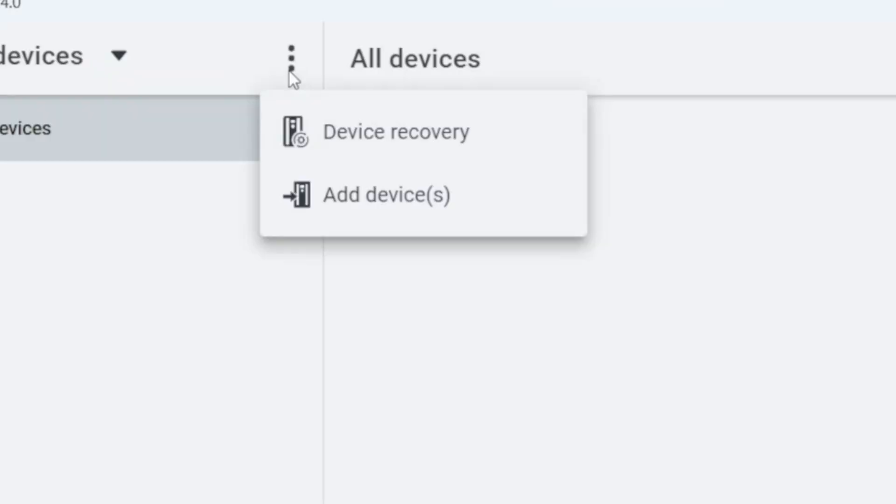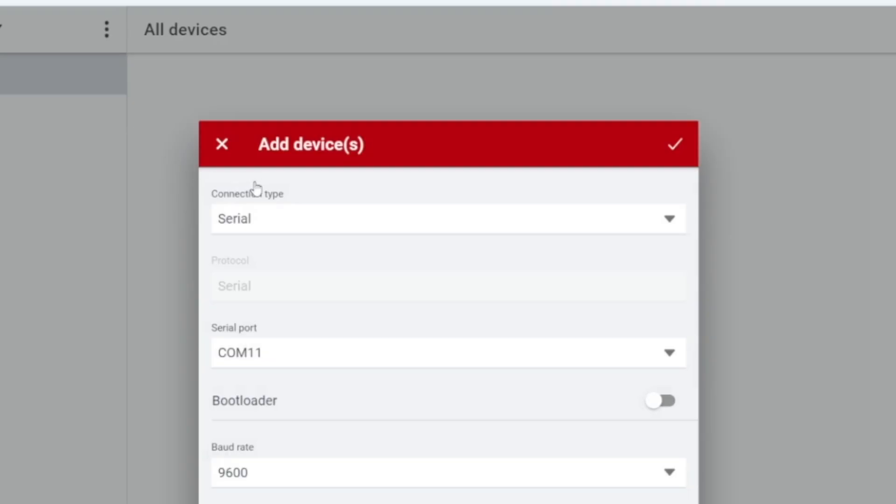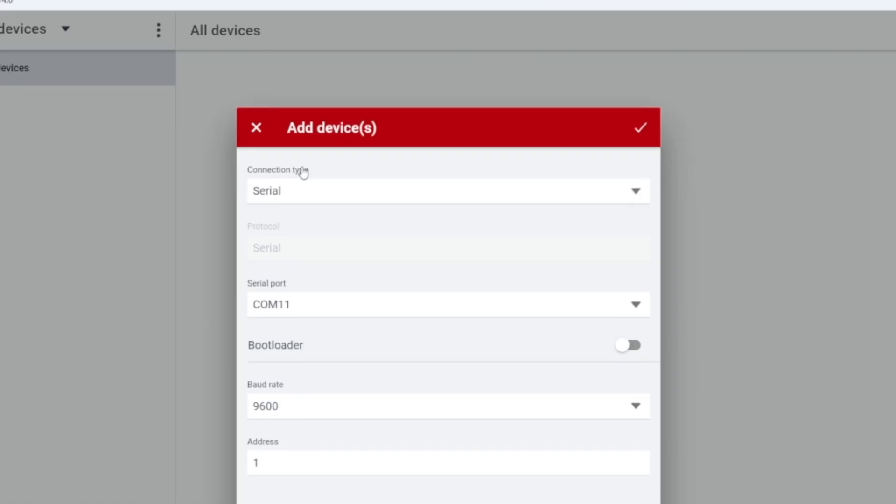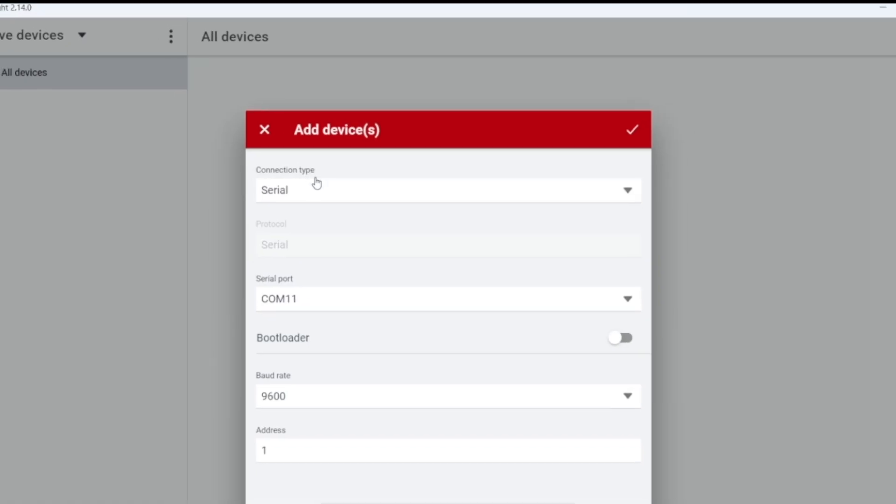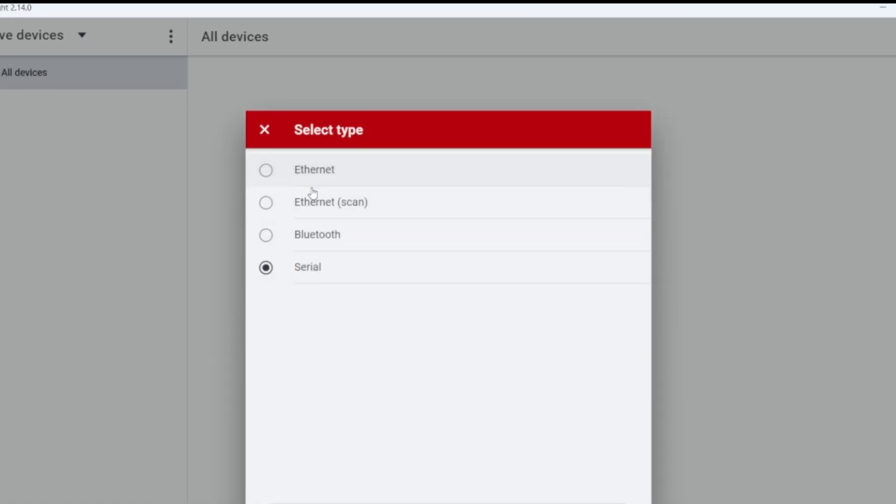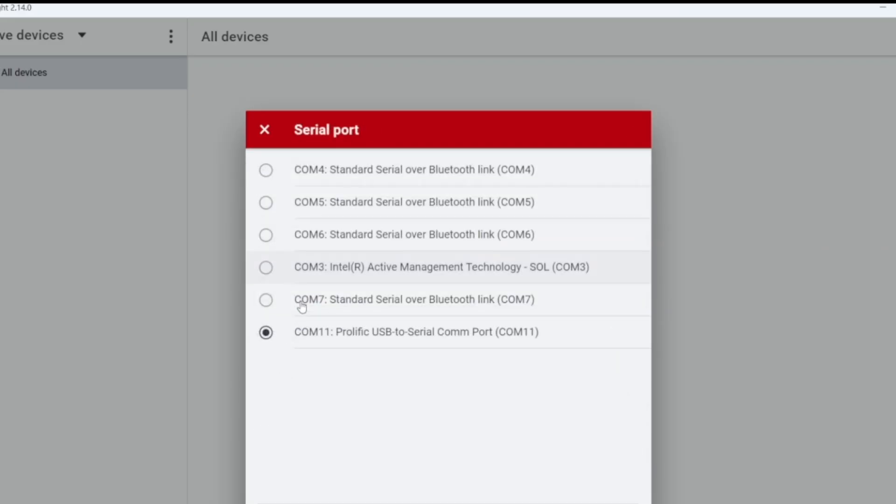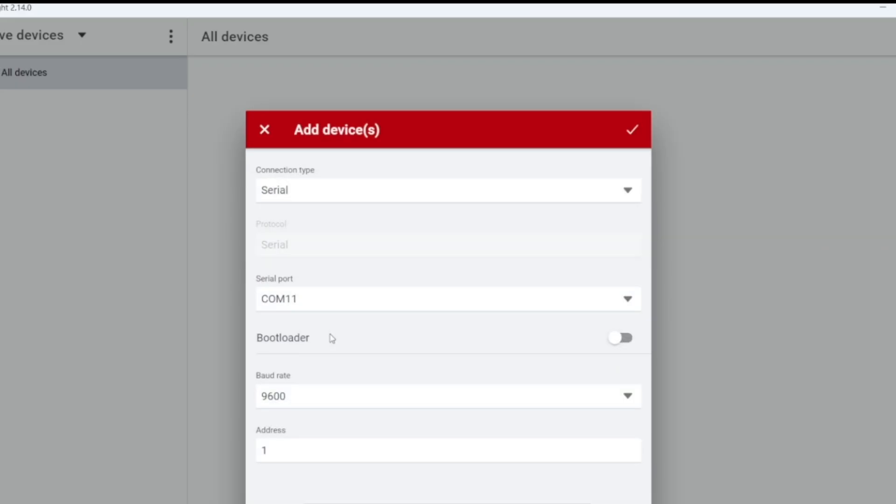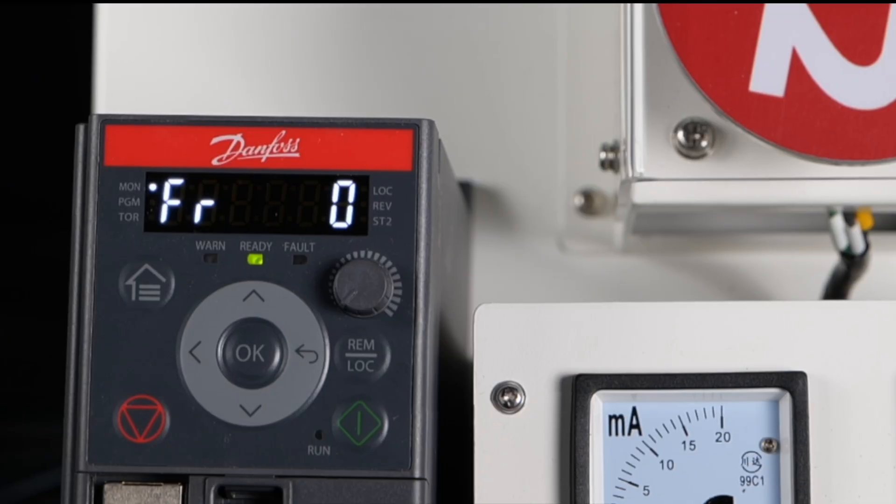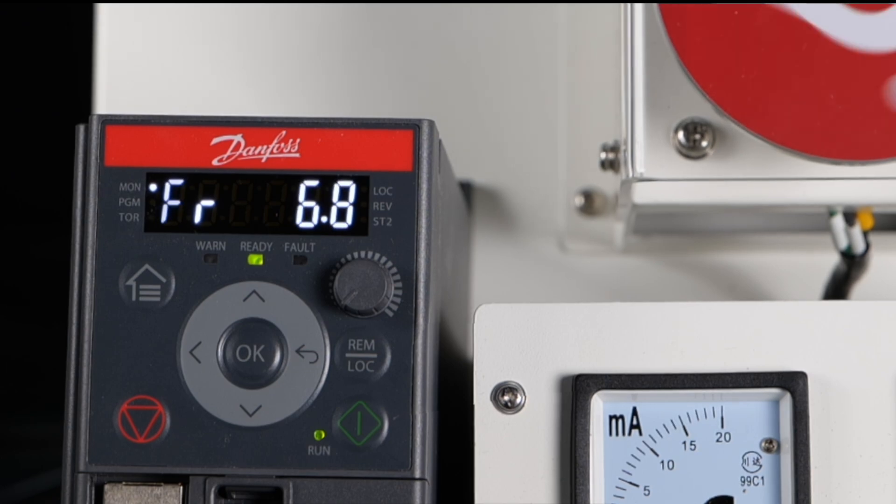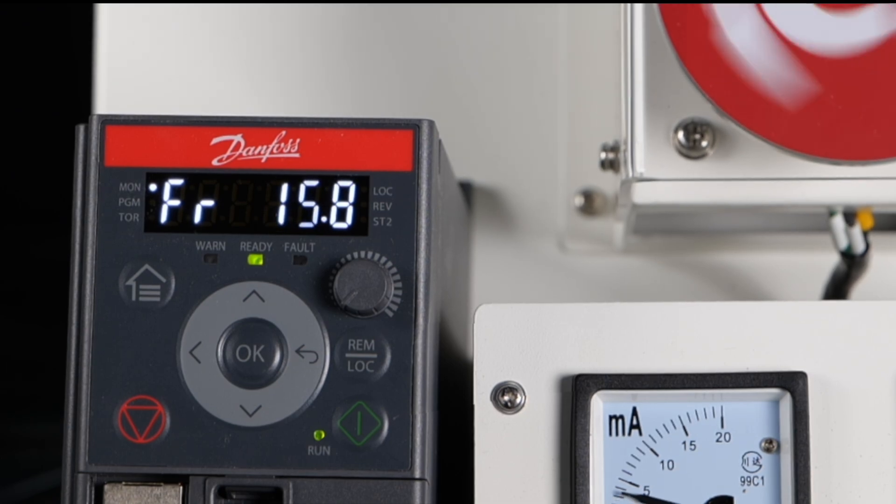Click the three dots in the upper left corner of the interface to select Add Device. Set the connection type to Serial and select the serial port which the computer is used for connecting. The default baud rate of IC2 micro is 9600, and the default address is 1. After the addition is completed, the communication indicator light of the frequency converter will light up accordingly.